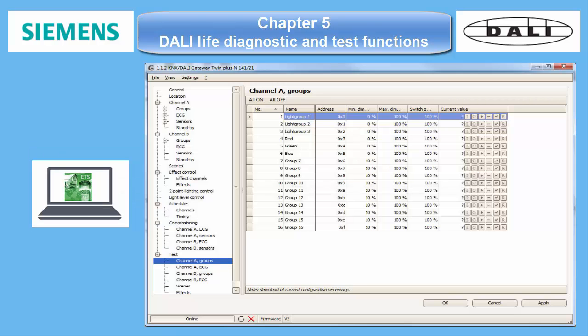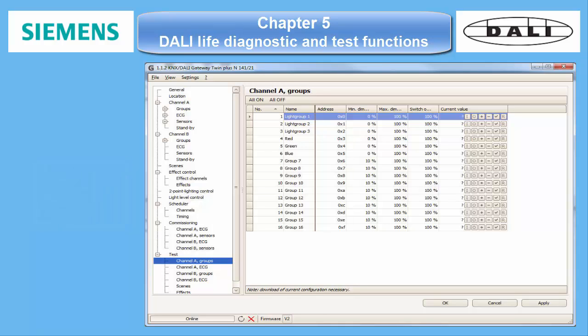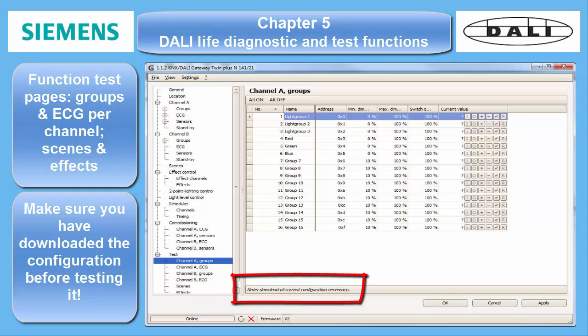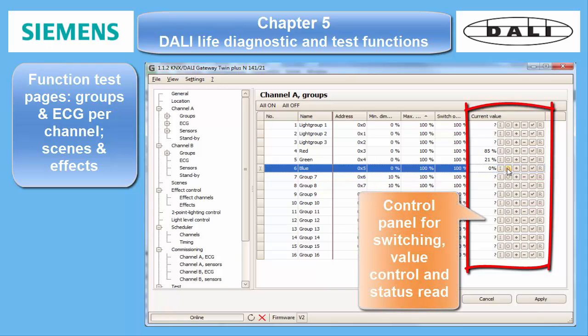After the commissioning of the ballasts and sensors, you can change to the test pages for groups, ballasts, scenes, and effects. If any of the operations doesn't work, the reason may be that you didn't download the configuration that you have made before.